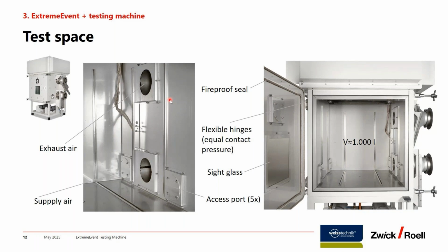Then in the front, you see there's a glass where you can see through to have a view inside the chamber. And with this additional locking system from Weiss Technik, you are safe that the door is closed, and inside, the flap mechanism, which here is on the top, that the flaps can go up during the pressure.